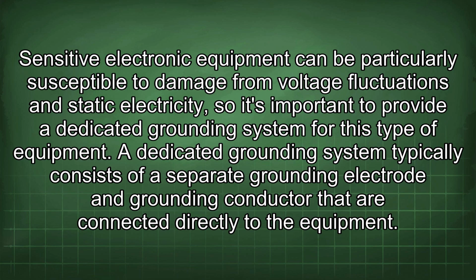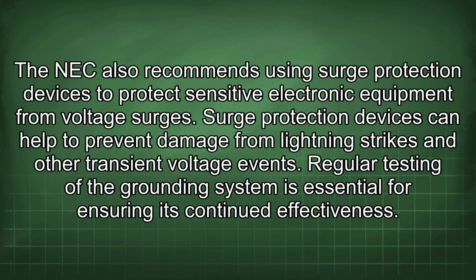A dedicated grounding system typically consists of a separate grounding electrode and grounding conductor that are connected directly to the equipment. The NEC also recommends using surge protection devices to protect sensitive electronic equipment from voltage surges. Surge protection devices can help to prevent damage from lightning strikes and other transient voltage events. Regular testing of the grounding system is essential for ensuring its continued effectiveness.